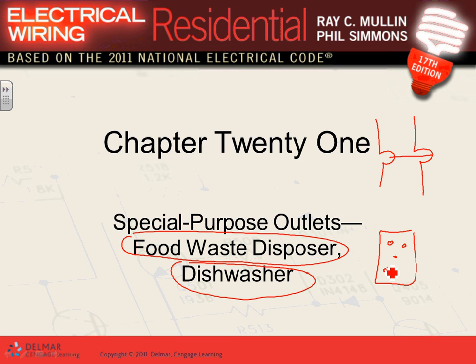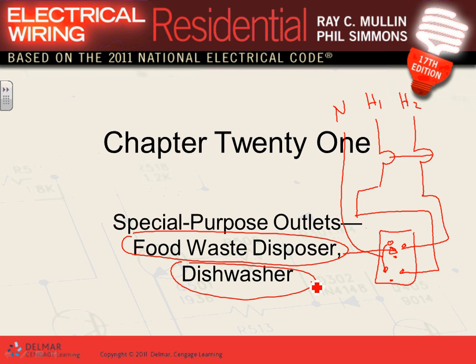We had the receptacle like this, and we had a split phase, one phase coming to this side, and the other phase coming to this side, or the other hot, and the neutral are tied together here and coming to neutral. So here's my hot one, here's my hot two, and then we plugged in the garbage disposal in one and the dishwasher in the other. That's how you designed it for me, right? And we brought two circuits to one receptacle, a split circuit receptacle, we call it.